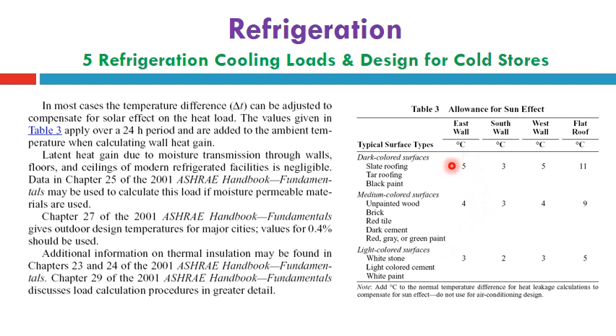Then we can find the additional temperature value if we have a dark colored surface in the refrigerated space, one of these types. The east wall should be considered as an additional 5 degrees in addition to the temperature listed for the major cities. For the northern wall, we should take into account 5 degrees additional for east wall and also for west wall. However, for south wall we have to add only 3 degrees Celsius additional, and for flat roof we add 11.